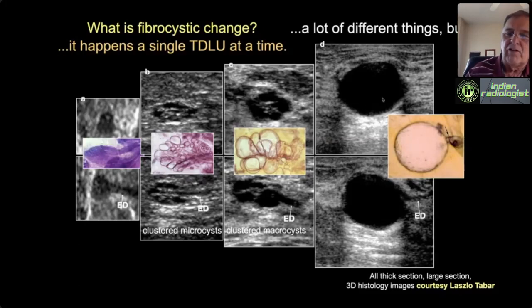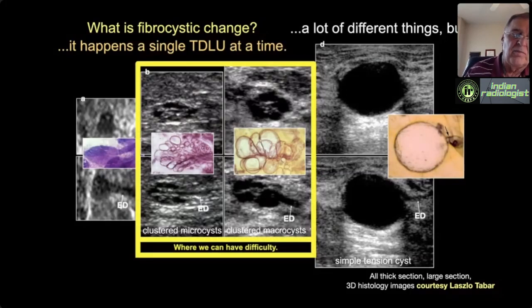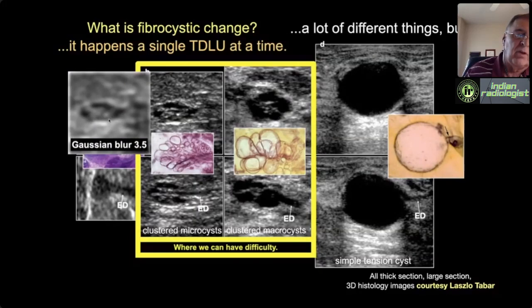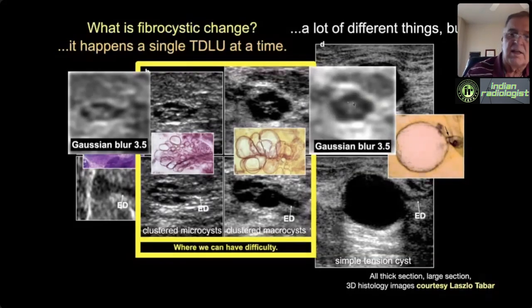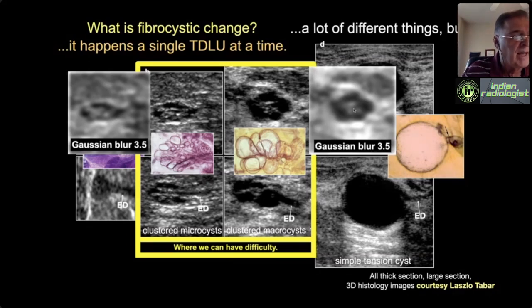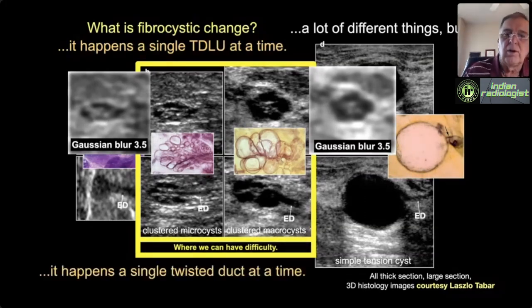We don't have trouble with normal TDLUs or simple cysts. But these in-between states of microcysts can cause problems because microcysts can be too small to resolve. If you volume-average white fibrous tissue with black microcysts, you get gray. I did a Gaussian blur in Photoshop and with lower resolution I can't resolve the microcysts—it looks like a solid isoechoic mural nodule or a thick septation. With lower-end, cheaper ultrasound machines you have less ability to resolve the microcysts, creating a falsely suspicious appearance of a complex cystic and solid mass.